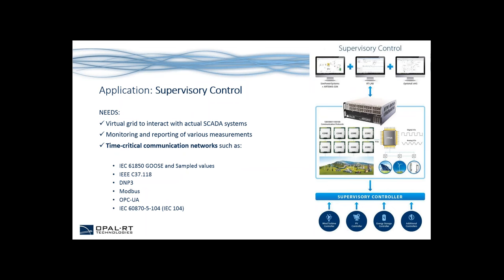The second application is supervisory control, where the real-time simulation interfaces with a supervisory controller or SCADA system. The virtual grid is simulated and interacts with an actual SCADA system. This requires monitoring various measurements and supporting time-critical communication networks such as IEC-61850, C37.118, DNP3, Modbus, OPC, and IEC-104, all integrated for supervisory control.